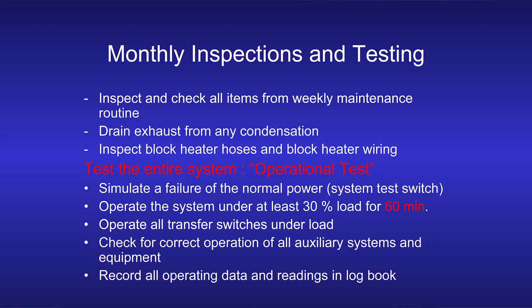That's quite an extensive list just on a weekly basis. Then you have monthly inspections on things that don't require as much monitoring and testing. One important part is that on a monthly basis you operate the system under load for 60 minutes. Diesel engines are more susceptible to problems if you don't have 30% load — they start doing what's called wet stacking, and they make a mess all over the outside of the engine block. So the code requires that you have at least 30% load available, which in most cases, if the engineers have done their job properly designing the system, you're going to have at least that minimum amount of load to test when the testing is done.